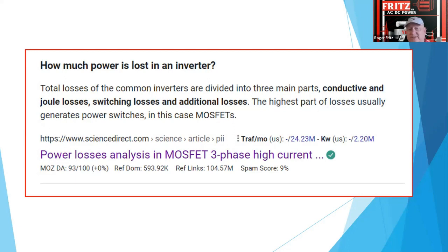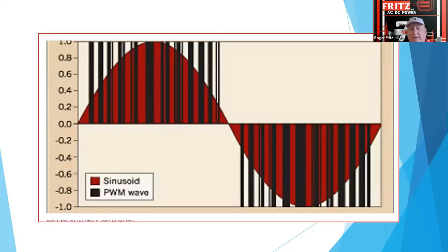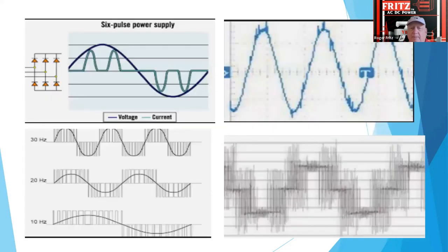Also, there are some losses inside the VFDs when you install them. You've got the effects of the transistors and the diodes, and it ends up being on average about 2 or 3% in power loss developing the power. Again, this shows the PWM as it's fired back out. We went over this already. Literally what we're doing is, if we slow the hertz down, normally it's 60 cycle, so you'll get 60 pulses of sine wave. On a 4-pole machine, if you do the math, the motor will run at 480 volts provided from the inverter, and at 60 cycle it will give full power and torque.